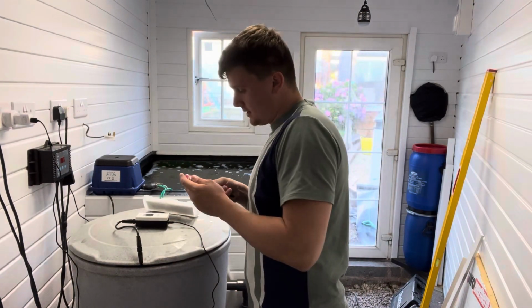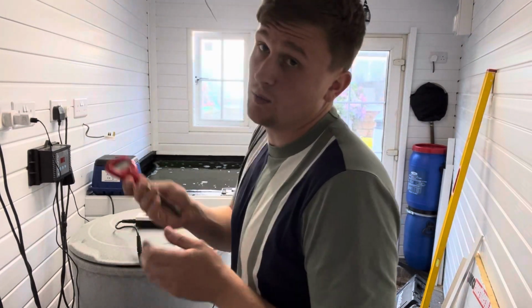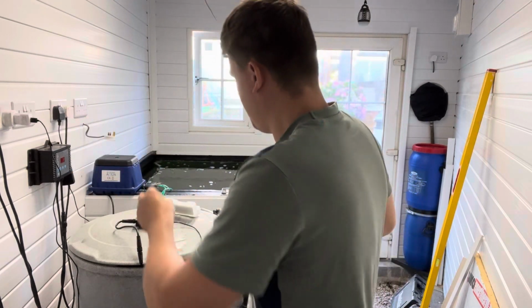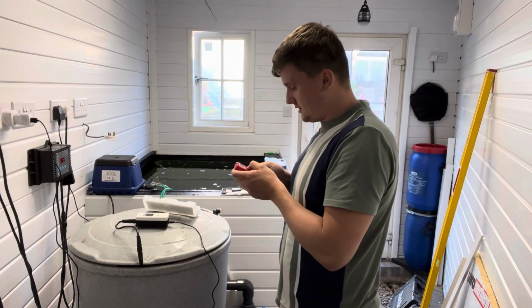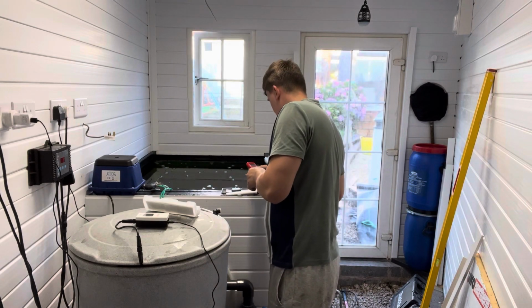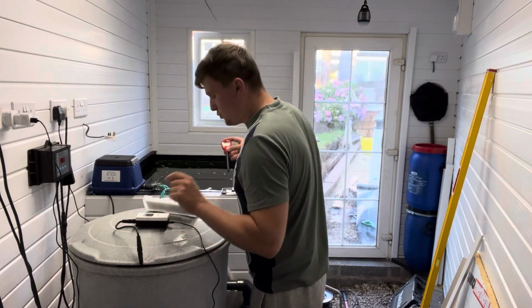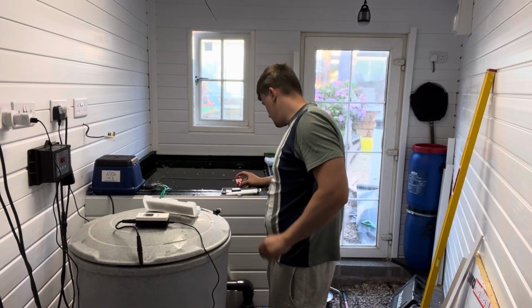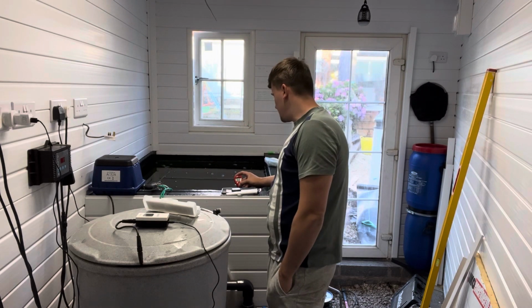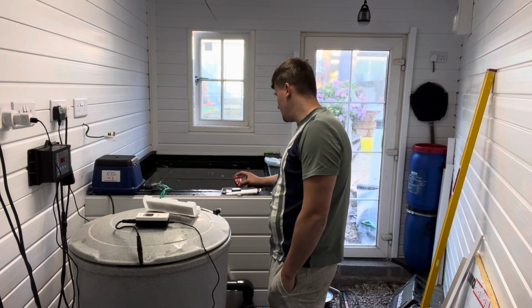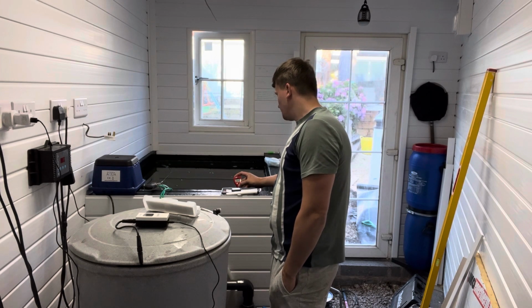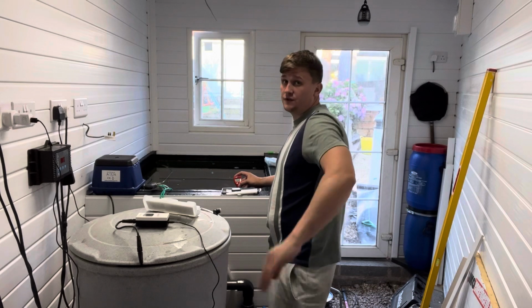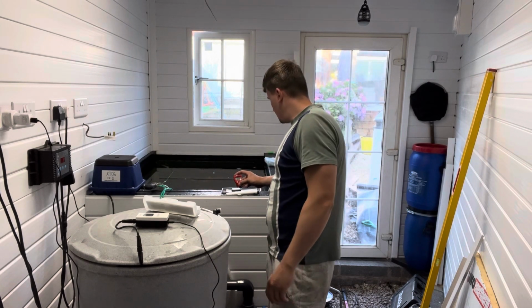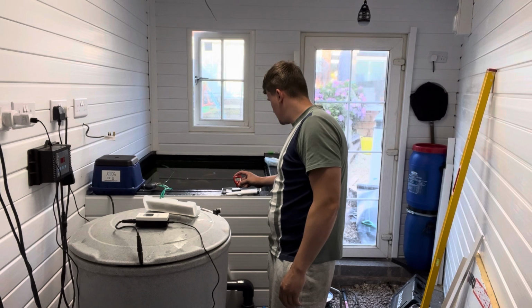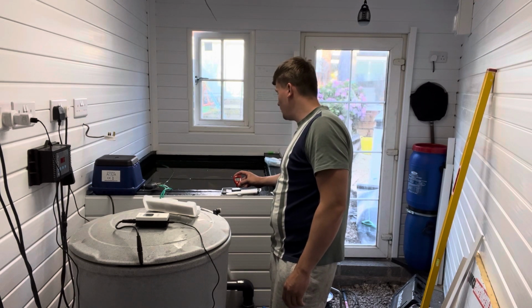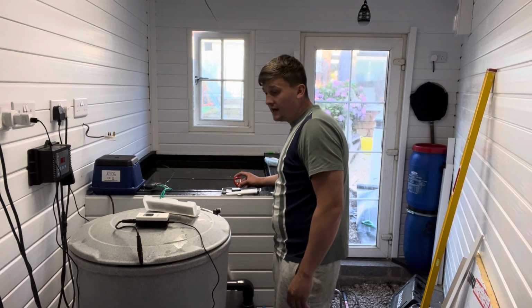So these are considered one of the best things to use for testing stuff. So this is already calibrated. So what do we say? We've got 8.16. So let's see. I'll give it a few seconds. It is around the 8 point something mark. I have turned everything off just for the sound quality, because I don't want the pump or anything. So we are slowly going down. I'm on 8.17 at the moment, and that was saying 8.16.